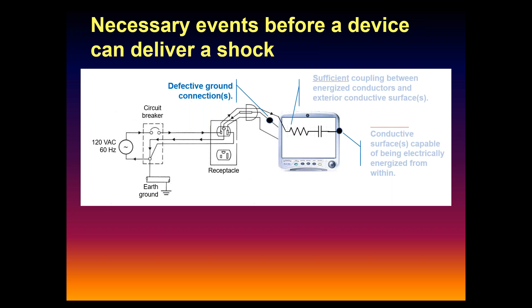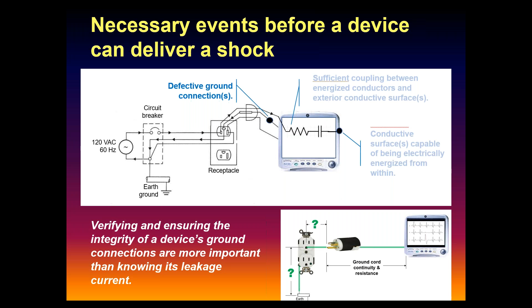This remains a good, viable thing to do — you've probably all seen ground resistance testing. If you've got a good, intact ground, it doesn't matter what the leakage current is. For semi-permanent devices, if you're really worried, you put a redundant ground on the device for extra protection. As long as that resistance is reasonably low, the leakage currents don't matter because they're going to drain away.